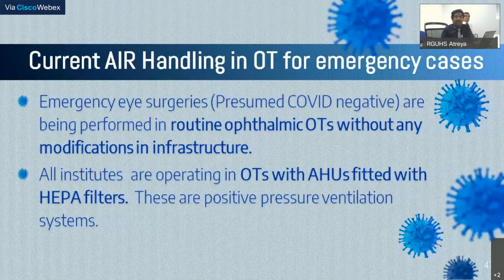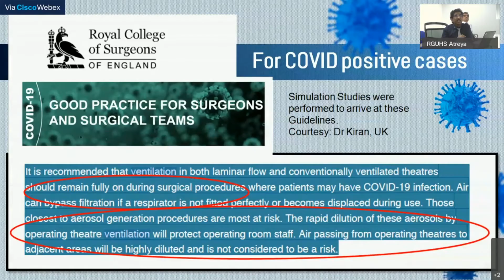As far as the air handling unit is concerned, this is the guideline from the Royal College of Surgeons of England, and it's very important to read. It says laminar flow and conventionally ventilated theaters should remain fully on during surgical procedures where patients may have COVID-19 infection. The rapid dilution of aerosols by the operating theater ventilation will protect the operating room staff. Air passing from the operation theater to the adjacent area will be highly diluted and is not considered a risk. This is a very important guideline from the Royal College of Surgeons.